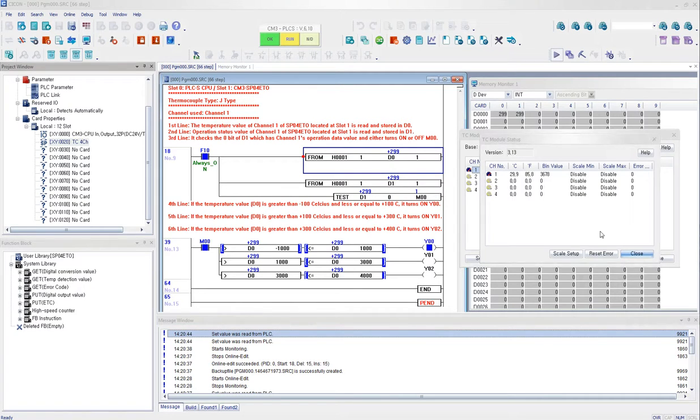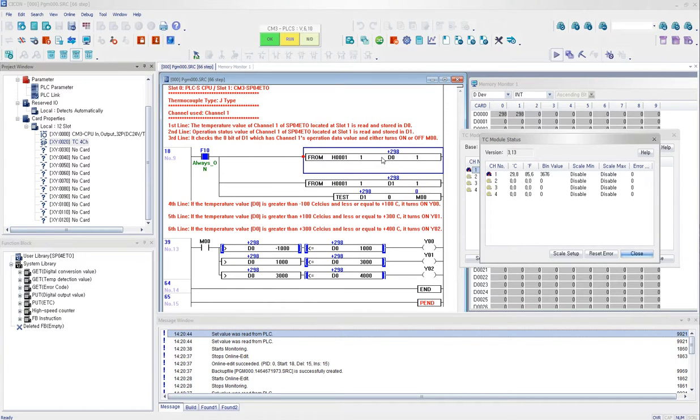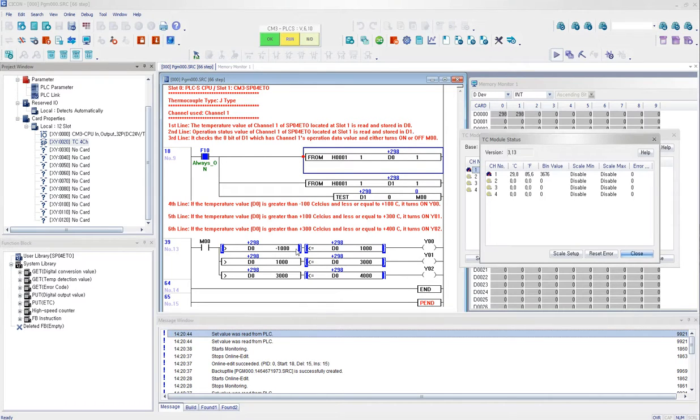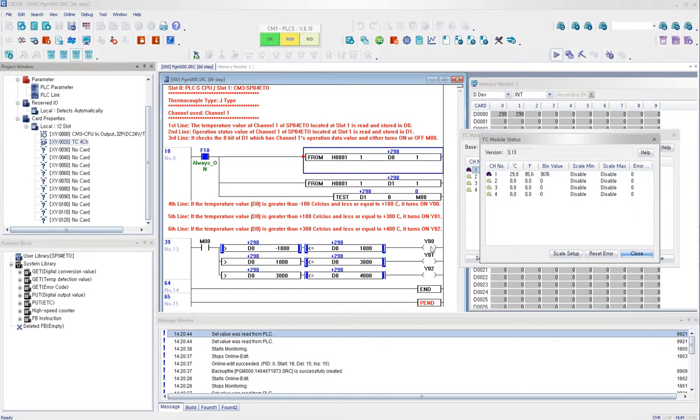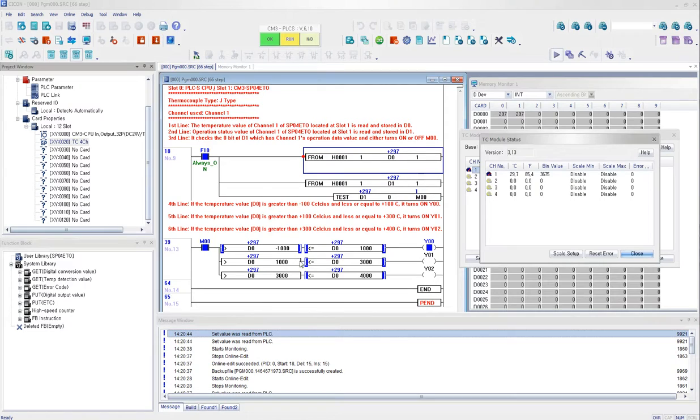Click on status and you can see my room temperature is 30 and it is 300 here. So the fourth line here, what I have configured is that my program tells me that if I have the temperature value from channel 1, and if the channel 1 temperature value is greater than minus 100 Celsius and less or equal to plus 100 Celsius, it will turn on the Y00 as it should. And if I have that value, the temperature channel 1 value greater than 100 Celsius and is less than 300, then it will turn on Y01.